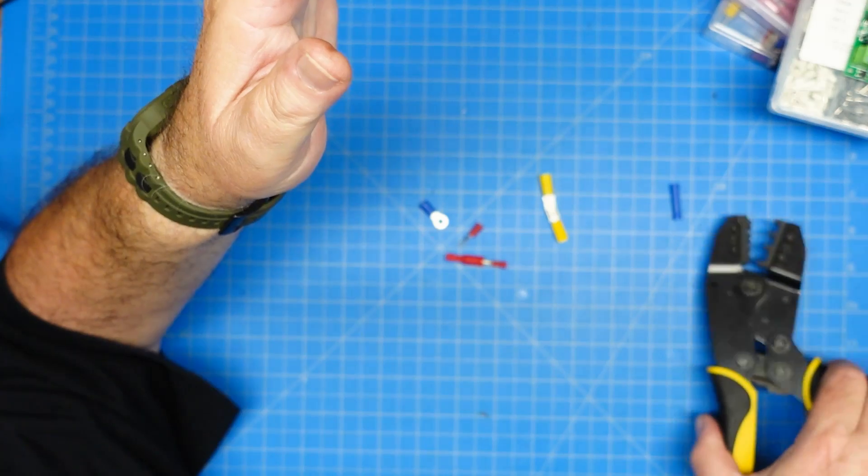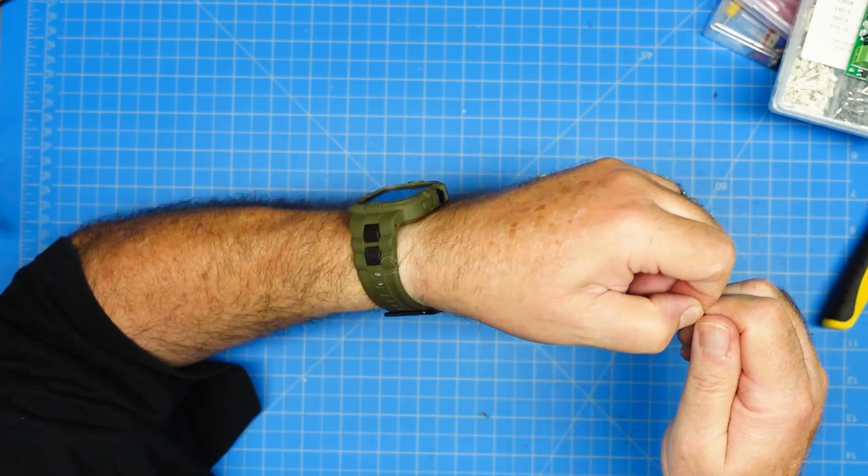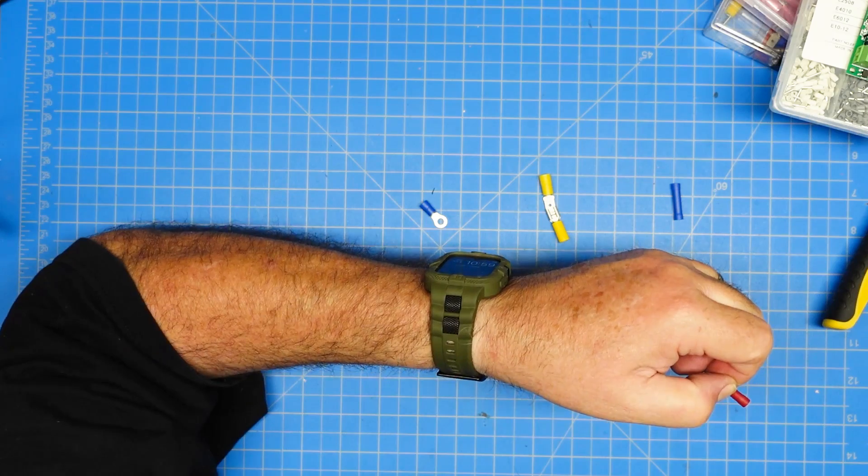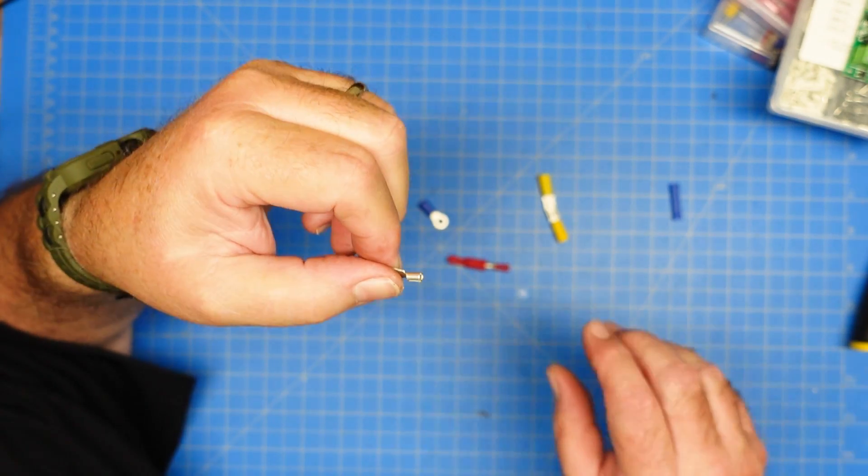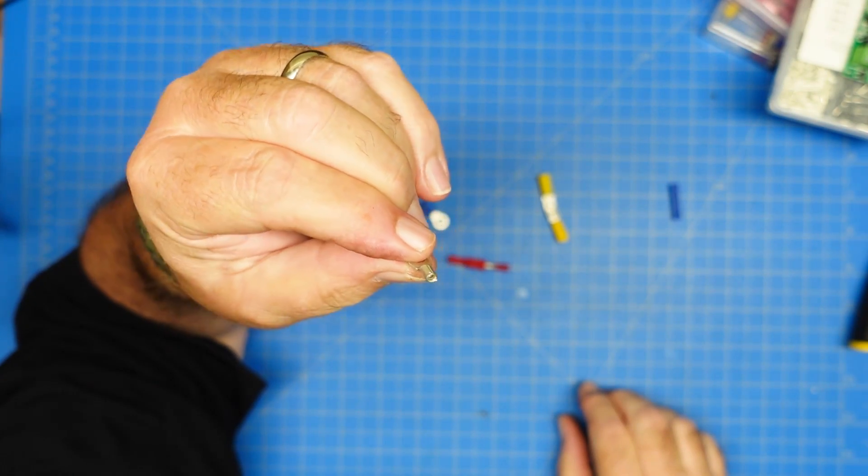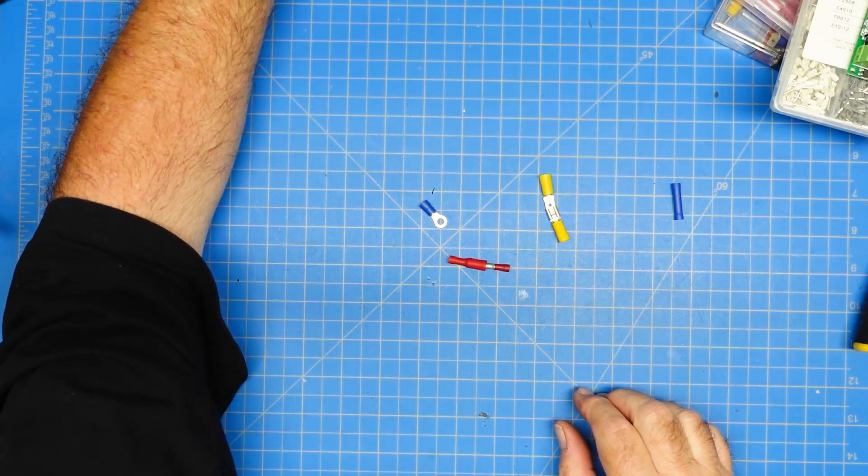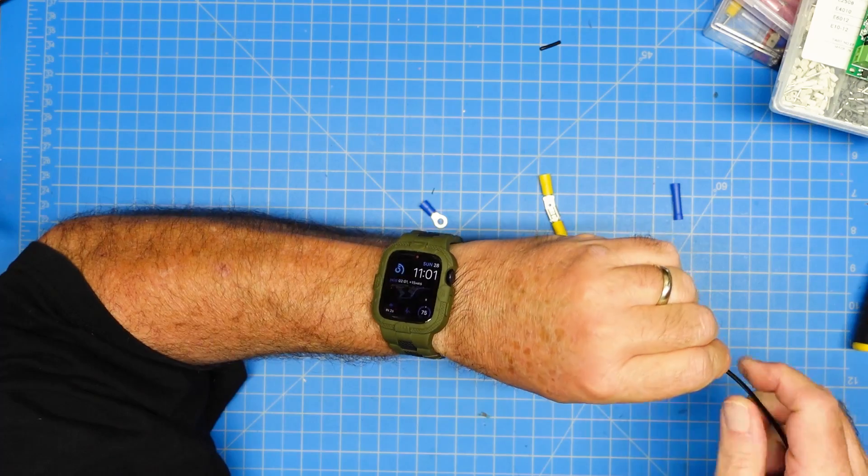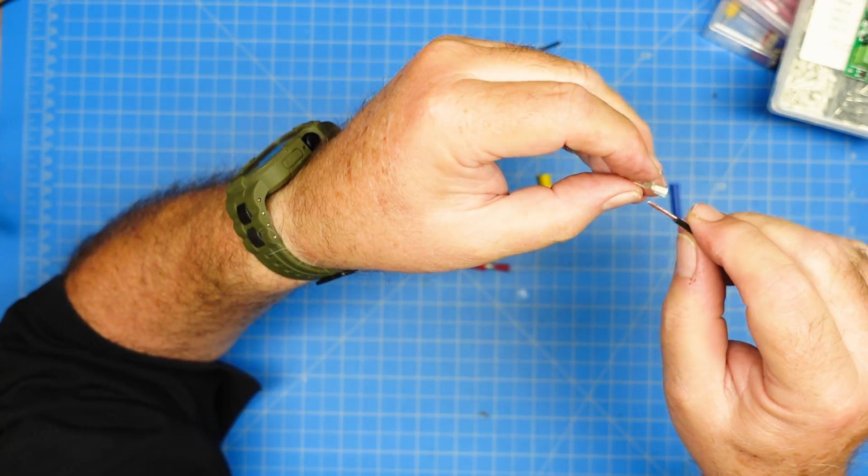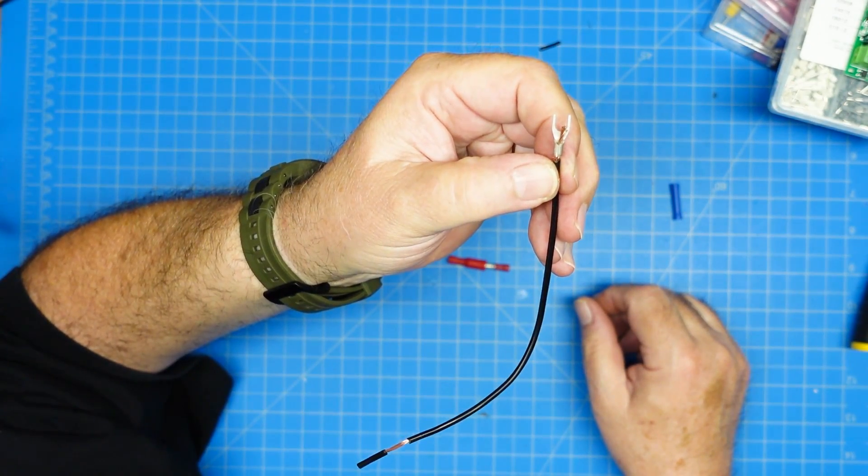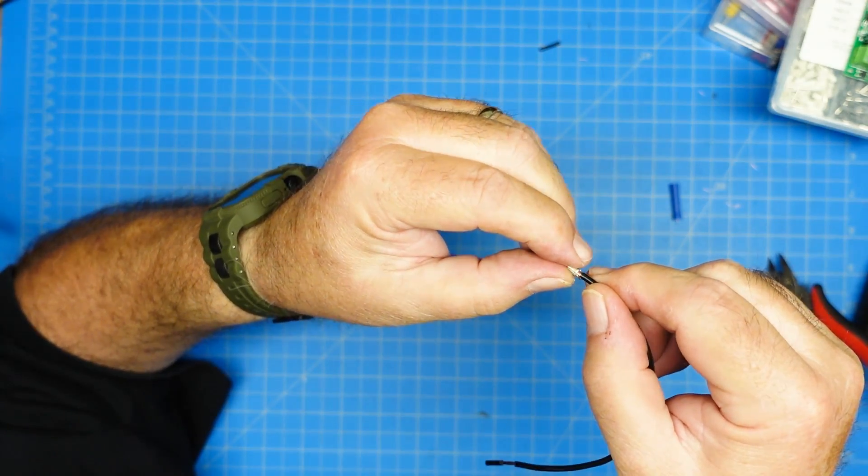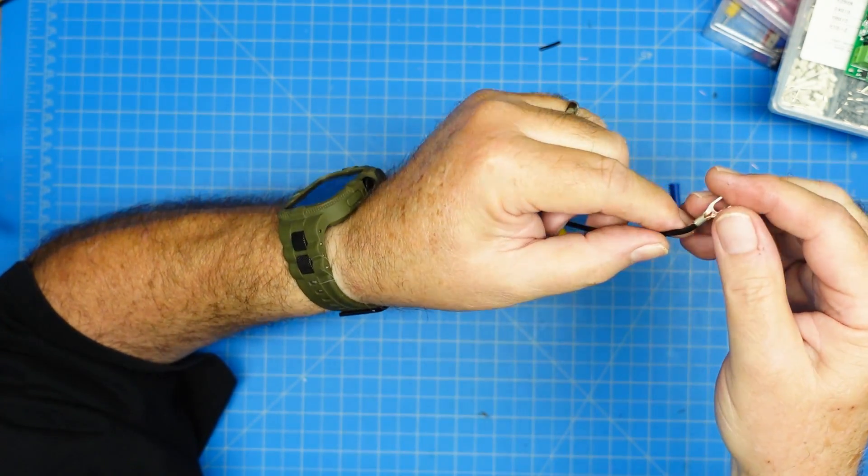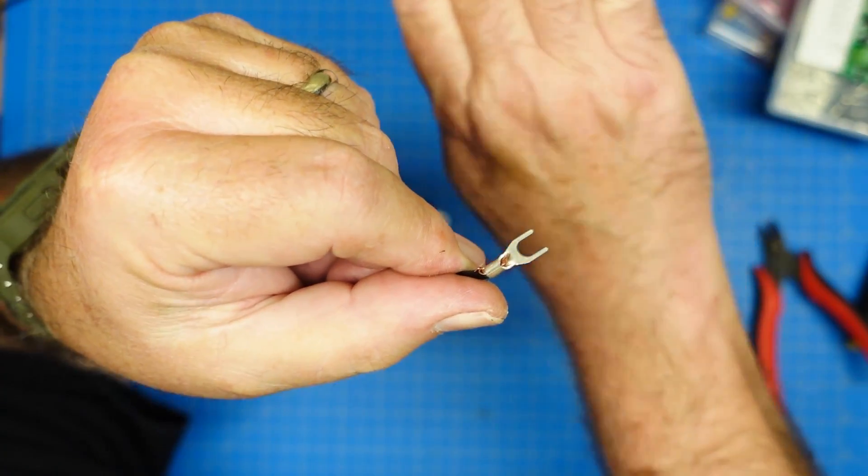The last thing I wanted to mention, since we talked about insulated connectors, which is what these are, a non-insulated connector is a little different. Let's see if I can make this a non-insulated connector. Okay, I just made a non-insulated connector. As far as I know, if you buy them non-insulated, they look exactly like this anyway. The difference is this now doesn't have the plastic on it. So if you're going to use a connector like this, for example, we're going to put this on this wire, and this is trimmed back way too much. The wire still goes in there the same kind of way. There we go. Now, obviously, that is way too much wire sticking out of that guy, so I'm going to grab my side cutters and trim that back. And I still have a little too much wire because I see silver sticking out down at the bottom, and I still need to trim that just a little more. So now that is a non-insulated connection right there. Alright? And you want to try and get all your wire inside the terminal. So there we go. Alright?